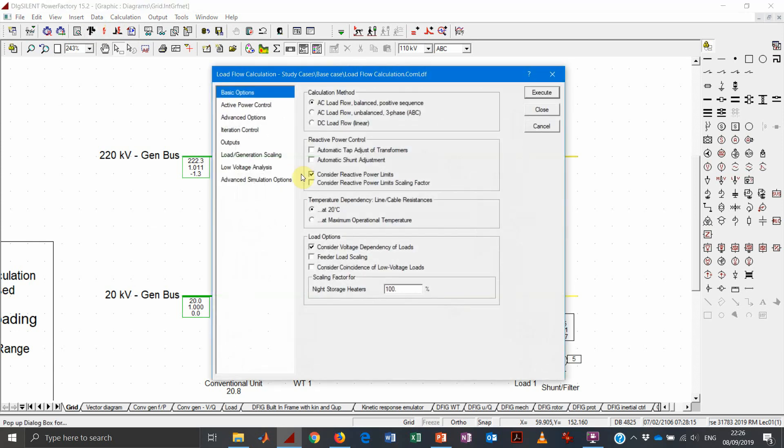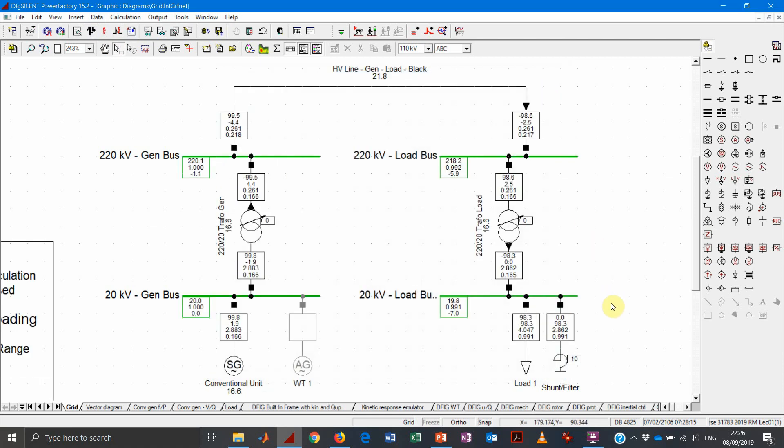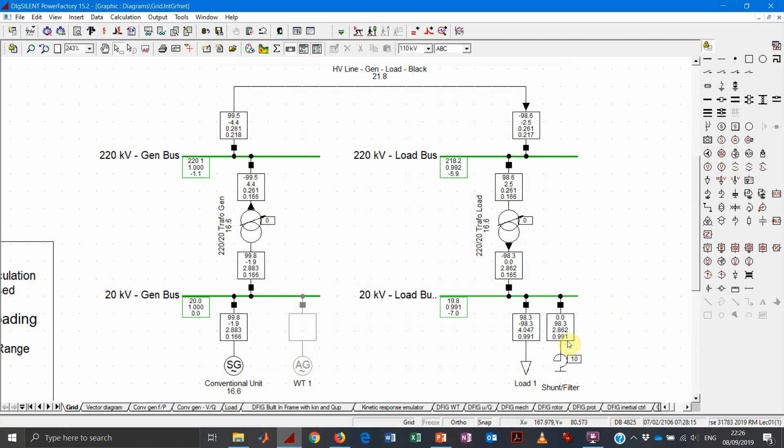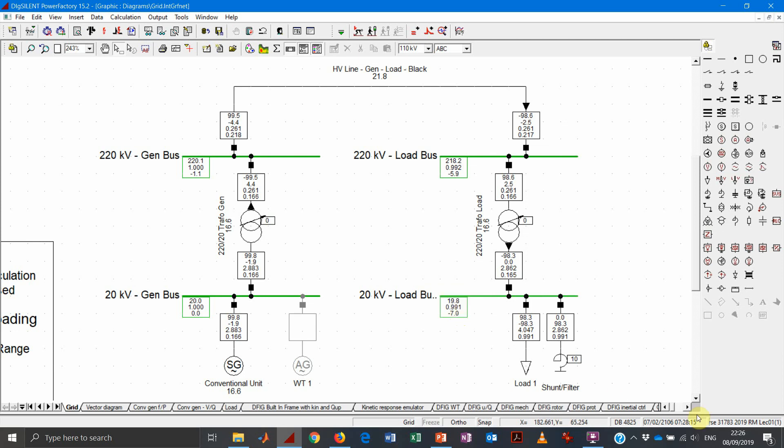Why? Because we need to also select this flag and let Power Factory adjust the shunt. And so in this case, we can see that, as one would expect, the shunt controller is going to deploy the whole reserve to fully compensate for the inductive load in the load, so that we hit the target voltage, which is one per unit.